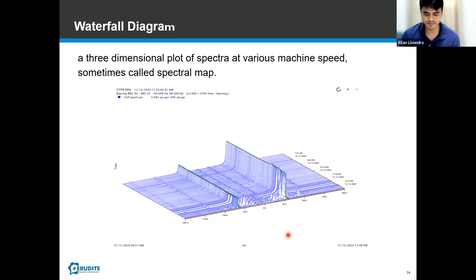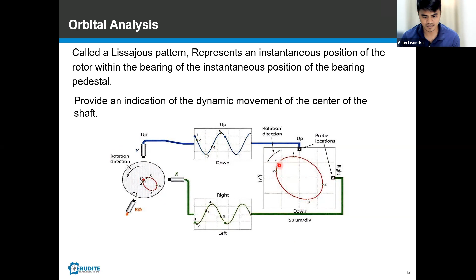Next we have orbital analysis, also called the Lissajous pattern, which represents an instantaneous position of the rotor within the bearing, or the instantaneous position of the bearing pedestal. It provides an indication of the dynamic movement of the center of the shaft. This is your probe, that's your Y and X, so this is your orbit — from the time waveform you get the orbit. This rotates clockwise or counterclockwise; this one is rotating counterclockwise.